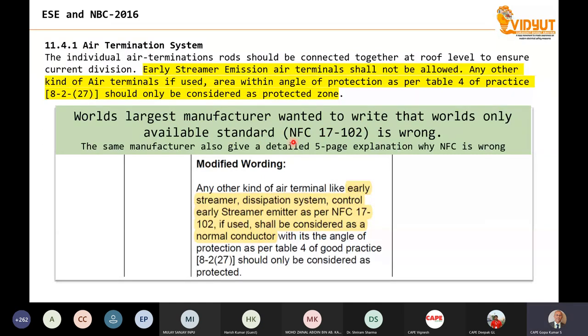Because if you read this, it's very clear. They say, don't use as per the only available standard. This is what they have written. So the world's largest manufacturer says that the world's only available standard is wrong. So what does the committee do? The committee said, okay, accept his wording and remove the standard which he has put. So the committee accepted the recommendation from this world's largest ESE manufacturer and put it as: any other kind of air terminal like dissipation system, ESE air terminal, CSE air terminal shall not be acceptable. Look at the wording. The wording itself came from the recommendation of the ESE manufacturer. So with one word, the whole problem is gone.